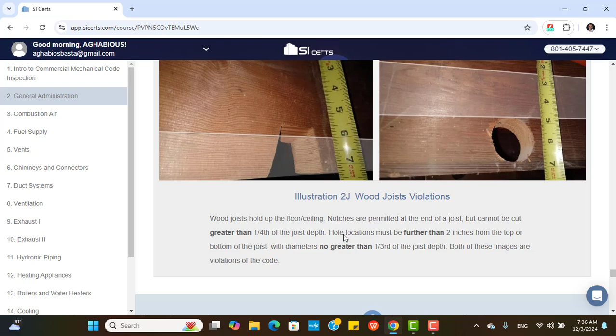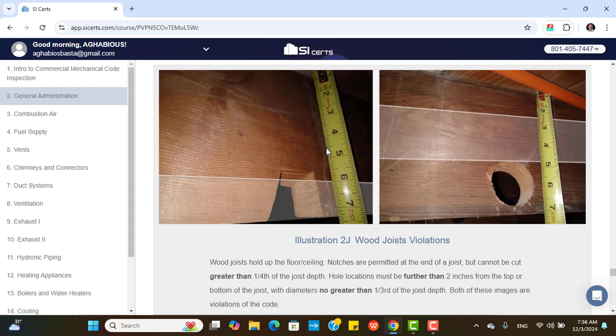the diameter must not be greater than a third of the depth, and it cannot be cut greater than a fourth of the joist depth. So this one and this one violate here, because as we see here, this one is about 5 inches. It's okay, but here it's about 1 inch or something, and here 0 inch.